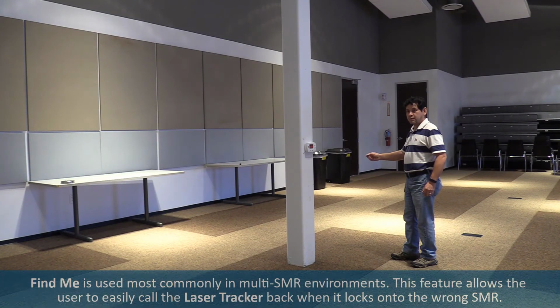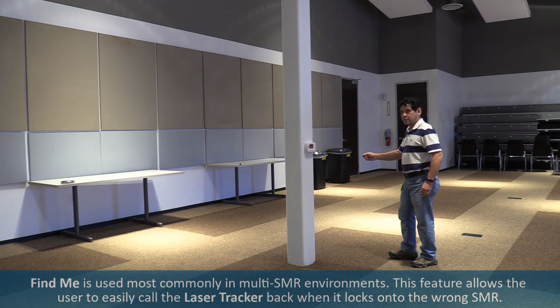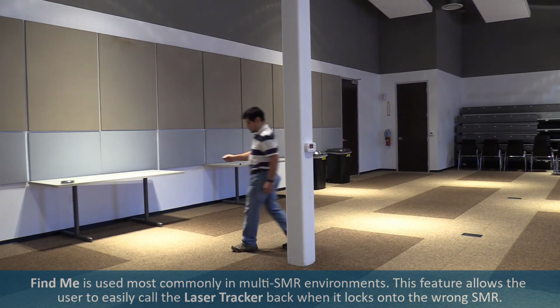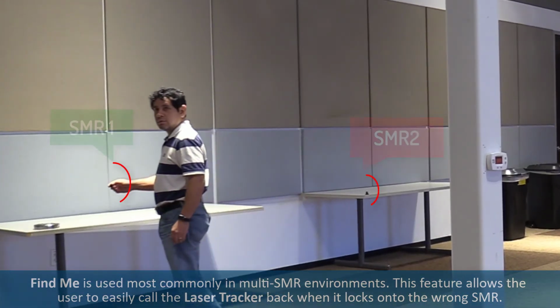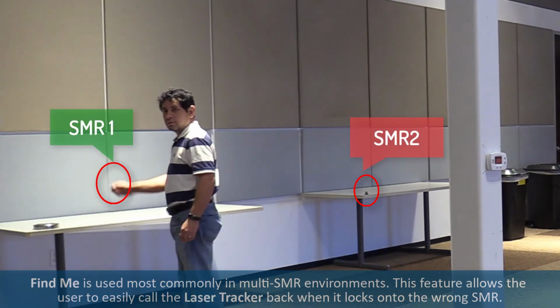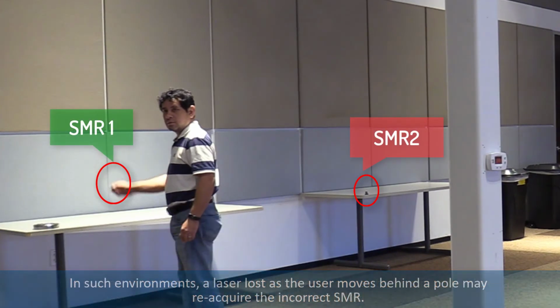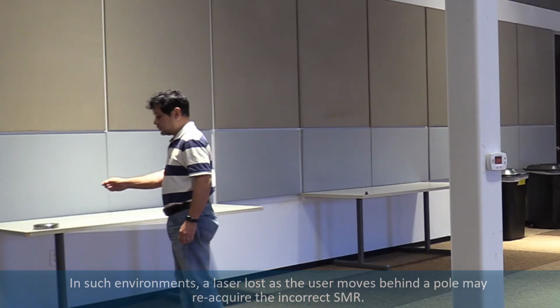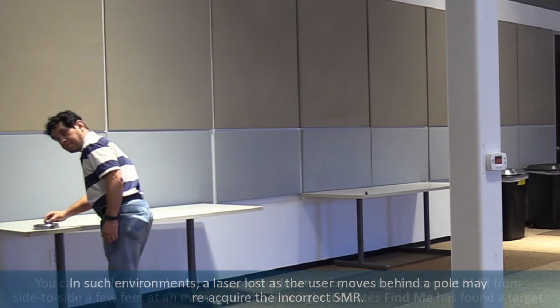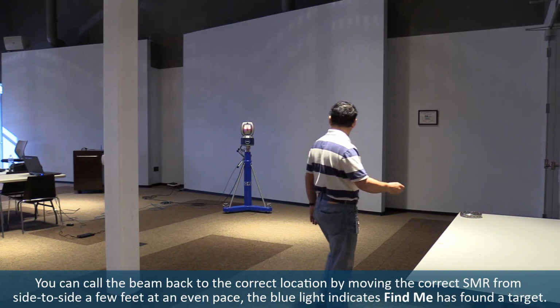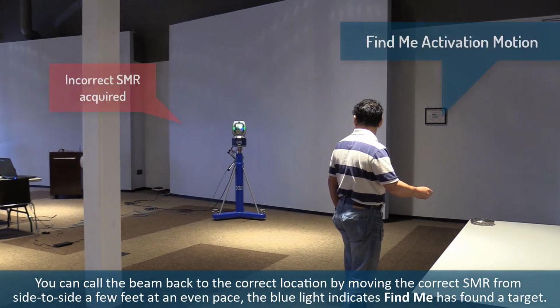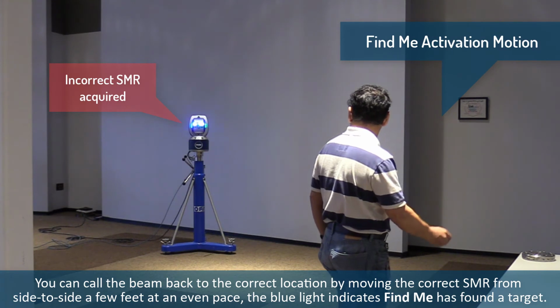FindMe is used most commonly in multi-SMR environments. This feature allows the user to easily call the laser tracker back when it locks on to the wrong SMR. In such environments, a laser lost as the user moves behind a pole may reacquire the incorrect SMR. You can call the beam back to the correct location by moving the correct SMR from side to side a few feet at an even pace.